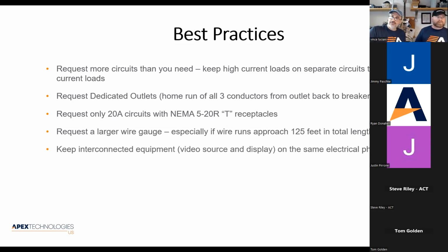And this is more important if you don't choose to use one of the power correction products that we're going to be talking about tomorrow. If you don't have any of that stuff, it's good practice to get connected equipment on the same phase. So you remember in our breaker panel example, it's phase A, phase B, phase A, phase B, phase A. So just ask your electrician, hey, everything that's going on my stuff, put it on phase A, right? And sometimes it's not a guarantee that if you mix your phases that you're going to have a problem. It's just that if you use the same phase all the time, you're reducing that.